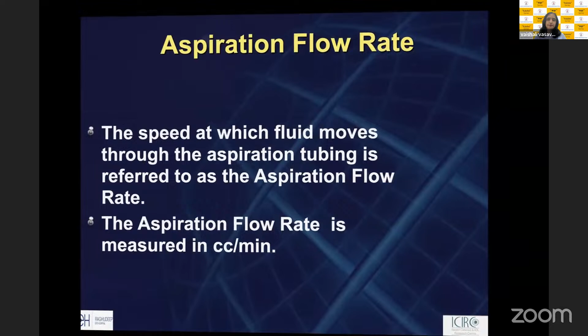What does it do? The flow rate is the rate at which fluid is drawn, which means it also decides the attractability, or what we call the followability in fluidic terminology. Followability is basically how much material is attracted to your phaco tip. It could be an IA tip, it could be a phaco tip. How fast the material is attracted depends only and only on your aspiration flow rate in a peristaltic system. All this, what I'm saying, holds true for peristaltic systems. So if I have a high flow rate, I'm drawing nucleus very quickly, which is good because it makes my surgery fast. But what is the downside? What is the downside of having a high flow rate?